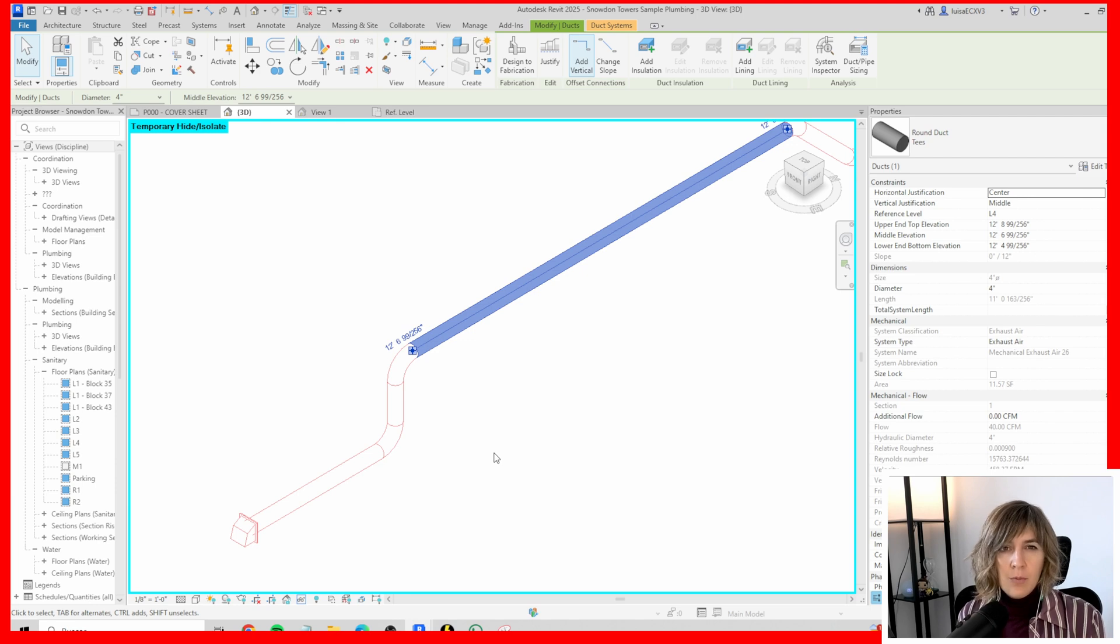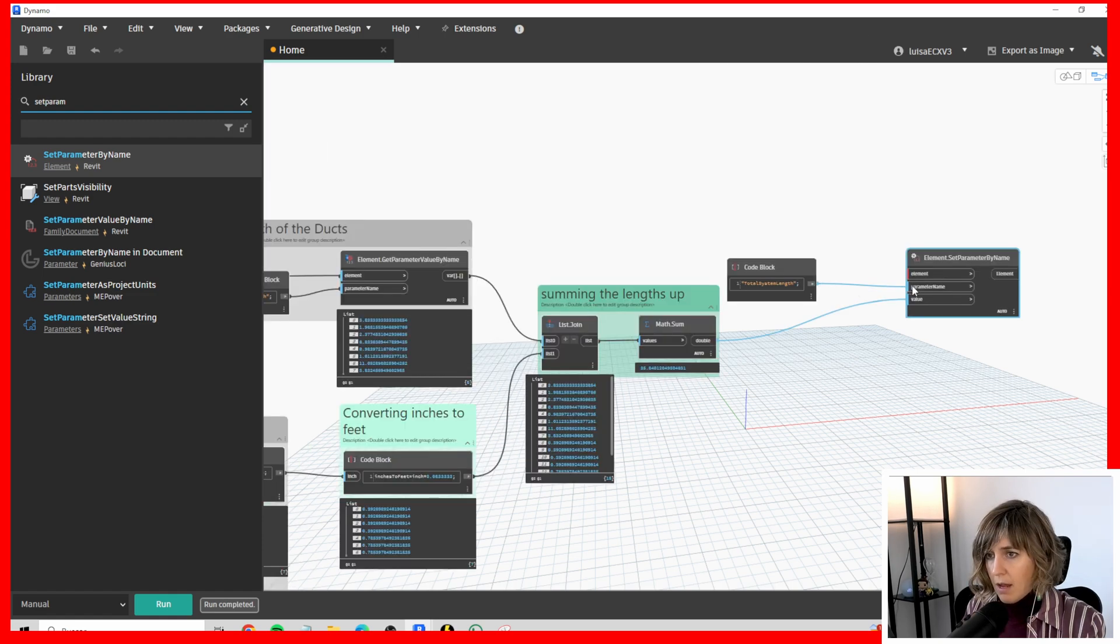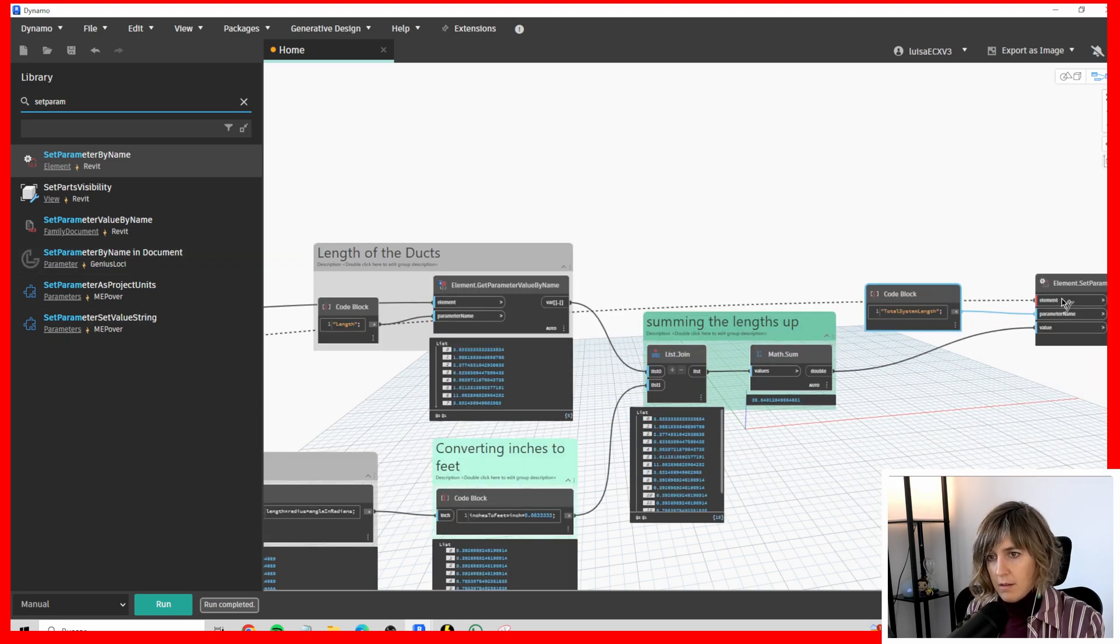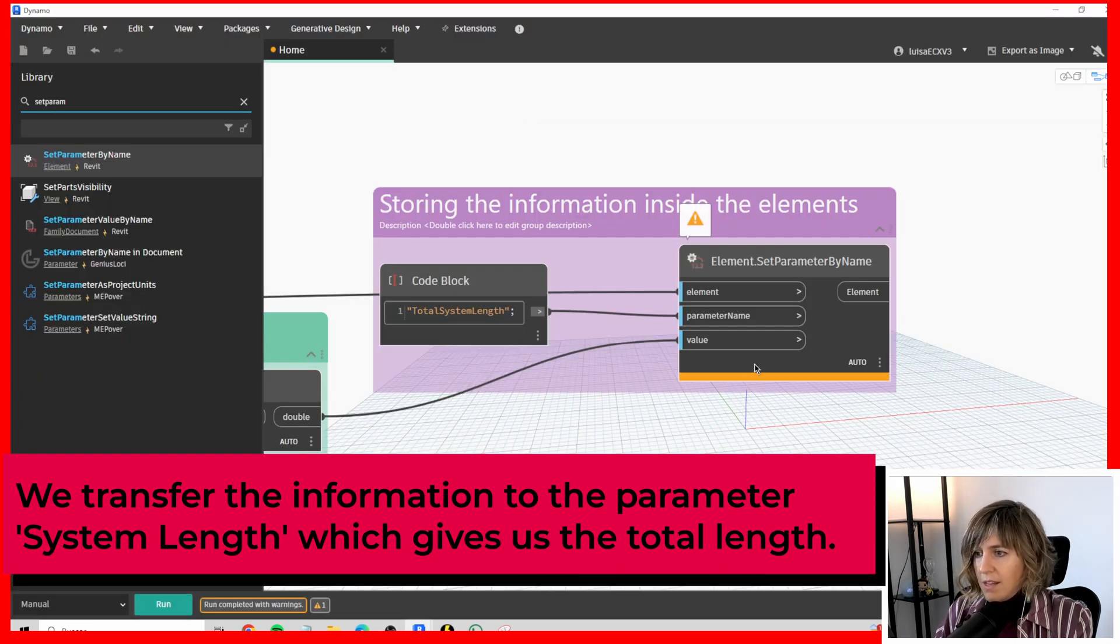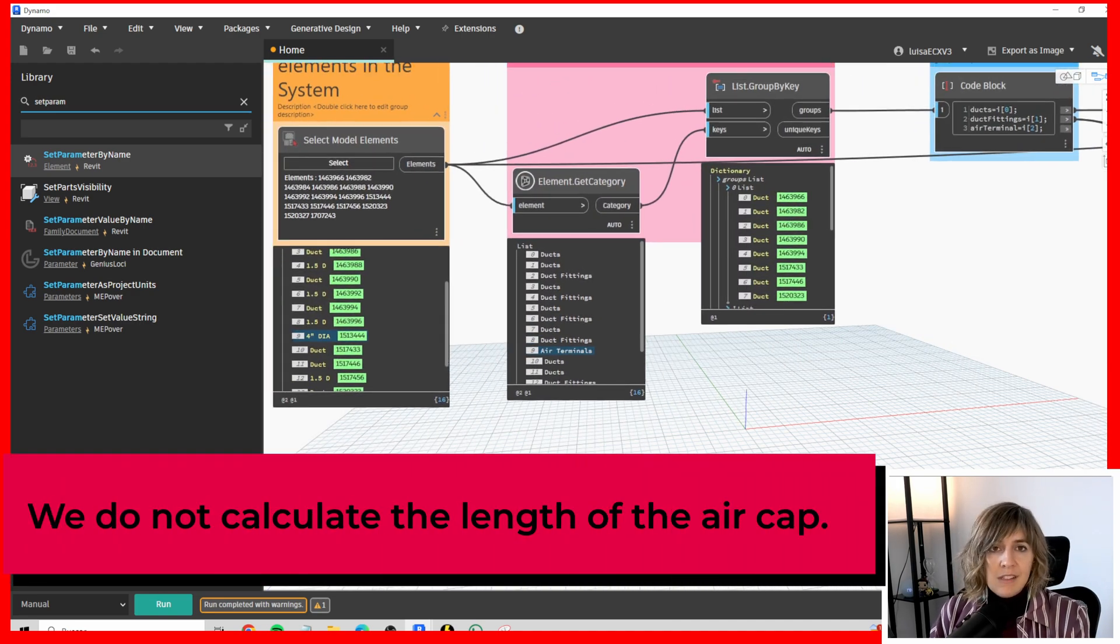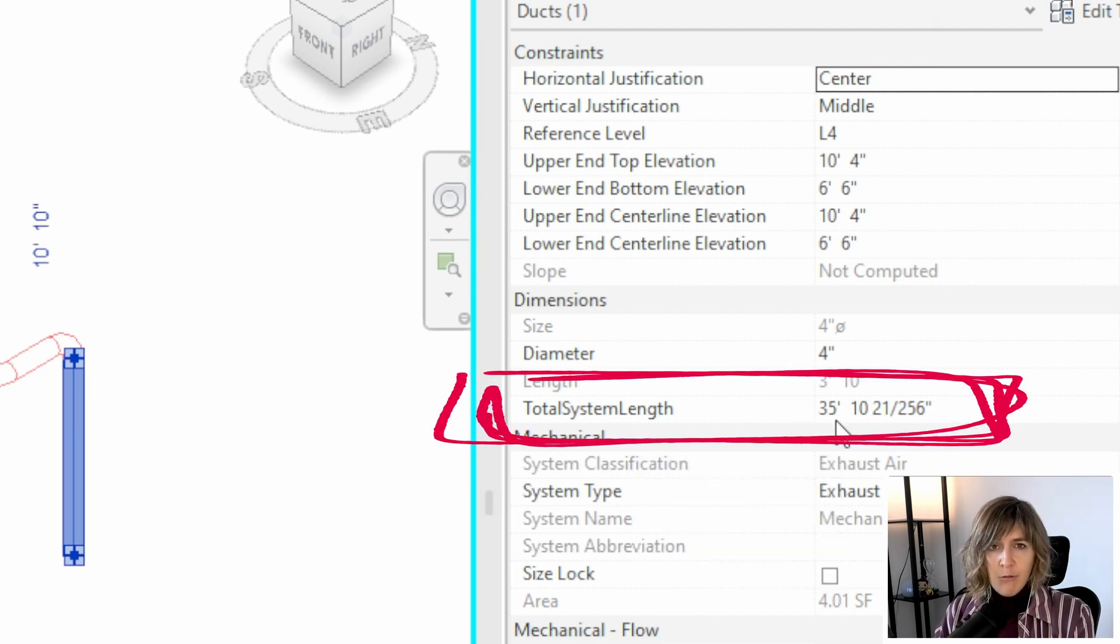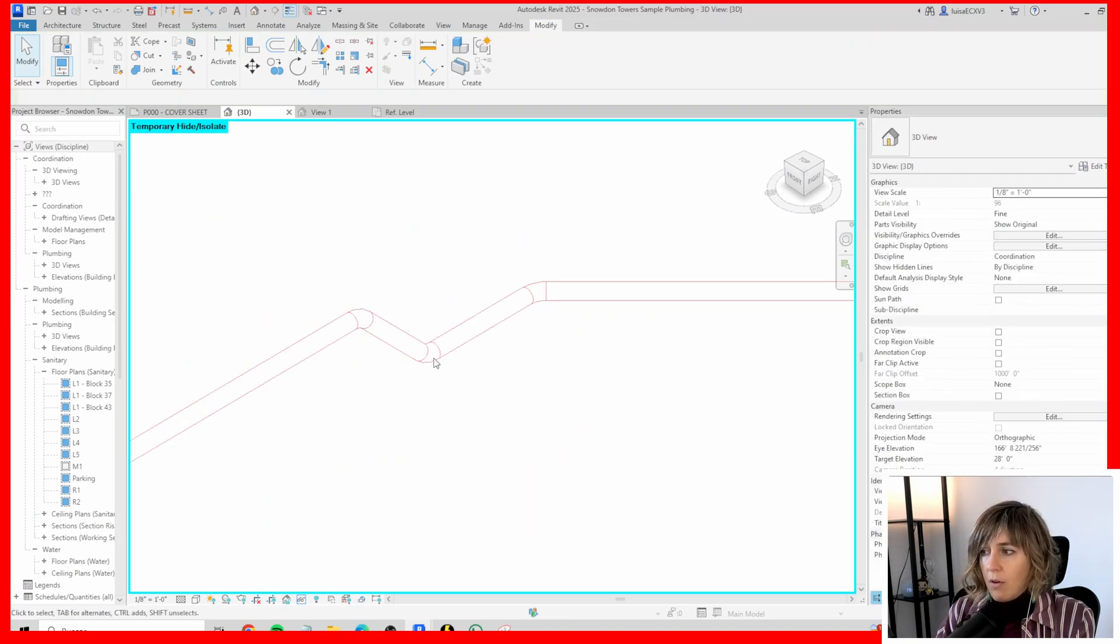Last step is to put that information inside our total system length parameter. Set parameter by name and we have here the value. The parameter name is total system length and our elements were right at the beginning all together. Let's run this. We do have a null element number nine which is our air terminal because I didn't introduce the total system length parameter in this air terminal. Let's check this up and here it is. The total system length 35 feet and 10 inches. Here I have this information in each and every element of the system. If you have found this video useful please don't forget to check our Dynamo Python mastery right here. And, of course you can subscribe to the channel. See you on the next one. Bye bye.